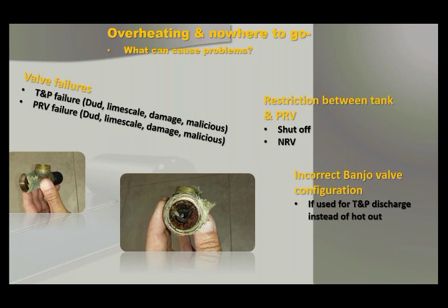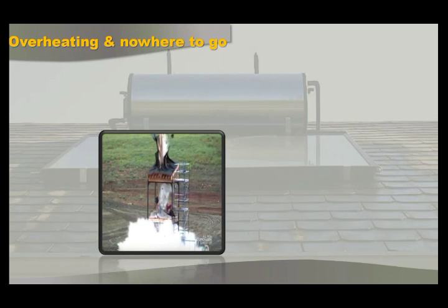So you open the tap, you say, yesterday I had lekker strong water, right now it's half the flow. Tomorrow, it's even less. You call a plumber, Mr. Plumber comes out and says, you've got this problem, I can replace the valve. So for that reason, that's where you put a banjo valve. And if it's not put like that, this is a problem that can occur.